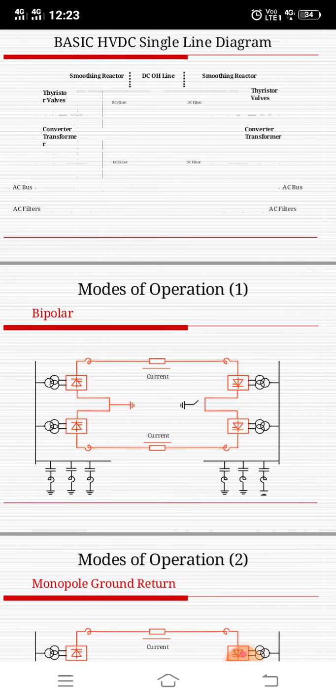The first type is bipolar with ground return path. This is a commonly used configuration for a bipolar transmission system. The solution provides a high degree of flexibility with respect to operation with reduced capacity during contingency or maintenance. The current of the sound pole will be taken over by the ground return path, and the faulty pole will be isolated.